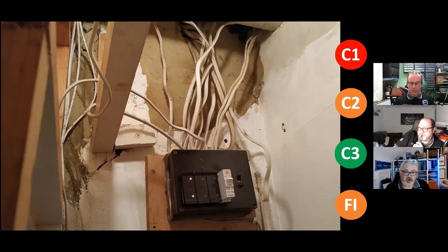Is that the whole board for the whole installation? Yes. Oh, yeah, okay. So there's way too much attached to it. Hang on, how many circuits are in it? A lot. There's only four circuits. Right, so, yeah, magic. Okay. That's a C2 there, isn't there, really? Yeah, the division of installation, all sorts. Yeah, we got C2. Wow.